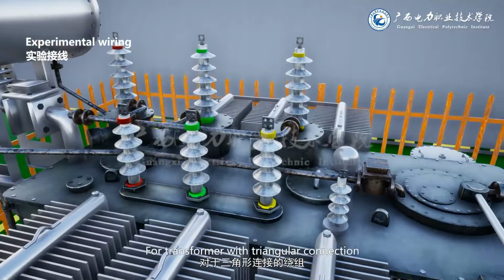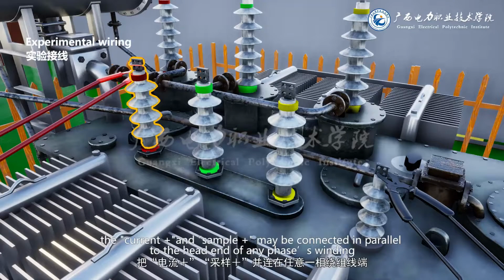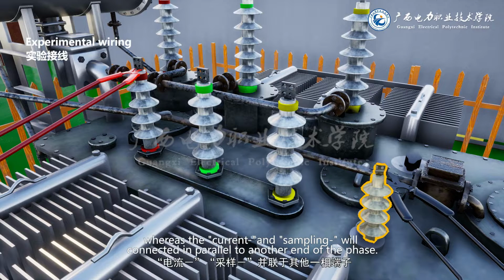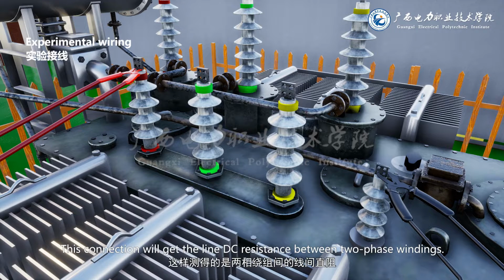For transformer with triangular connection, the current plus and sampling plus may be connected in parallel to the head end of any phase winding, whereas the current dash and sampling dash will be connected in parallel to another end of the phase. This connection will get the line DC resistance between 2 phase windings.